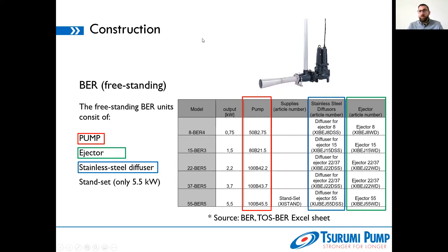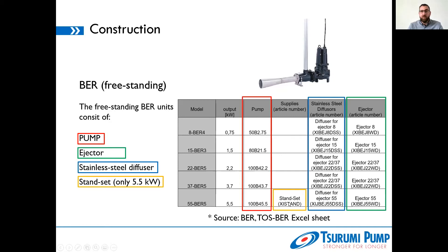For the freestanding version, we don't have a pump hanging in installation accessories — it needs to be freestanding, and thus you will need a separate stand. The smaller pumps have integrated feet, but as you may know from our B-series, pumps from 5.5 kilowatt onward need separate stand feet. So for the 100B 4 5.5 you will not only need the suitable freestanding ejector and the diffuser for the ejector 55, you will also additionally need the stand set. Please keep that in mind — if you order without the stand feet, you will not be able to install the unit freestanding.